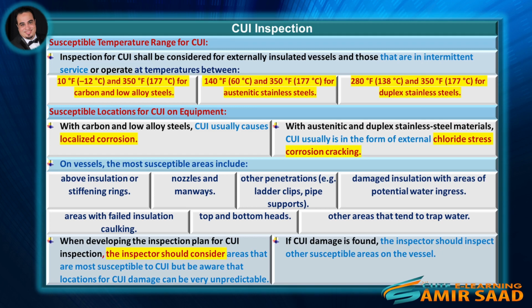On vessels, the most susceptible areas include above insulation or stiffening rings, nozzles and manways, other penetrations, for example ladder clips, pipe supports, damaged insulation with areas of potential water ingress, areas with failed insulation caulking, top and bottom heads, other areas that tend to trap water.